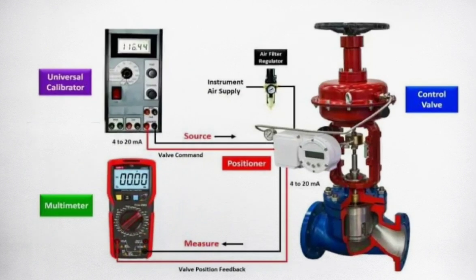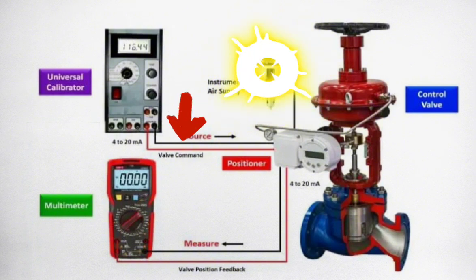Isolate the instrument supply air and vent the remaining air in the supply line to check the control valve fail action. Restore the instrument air tubing after making the valve normal and check the fail action after removing the signal cable.